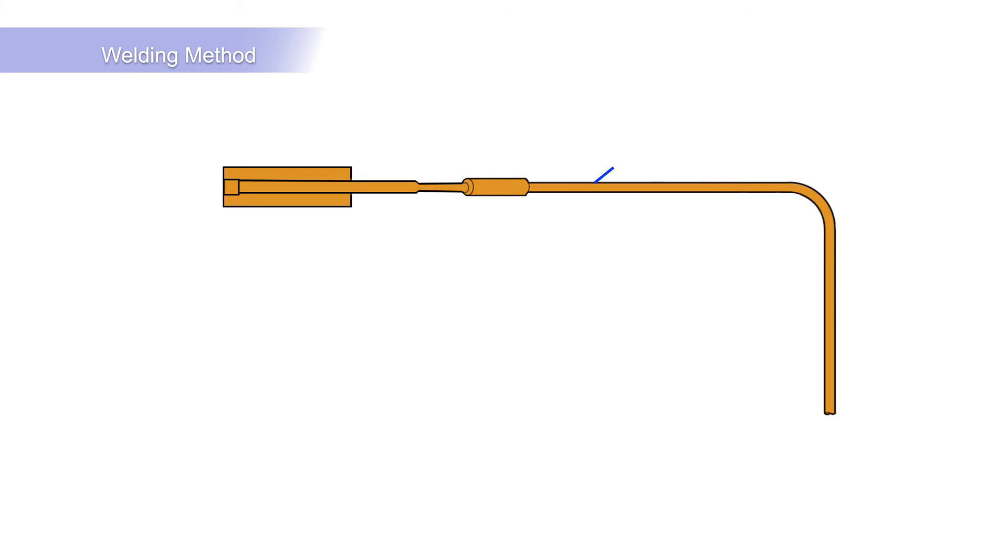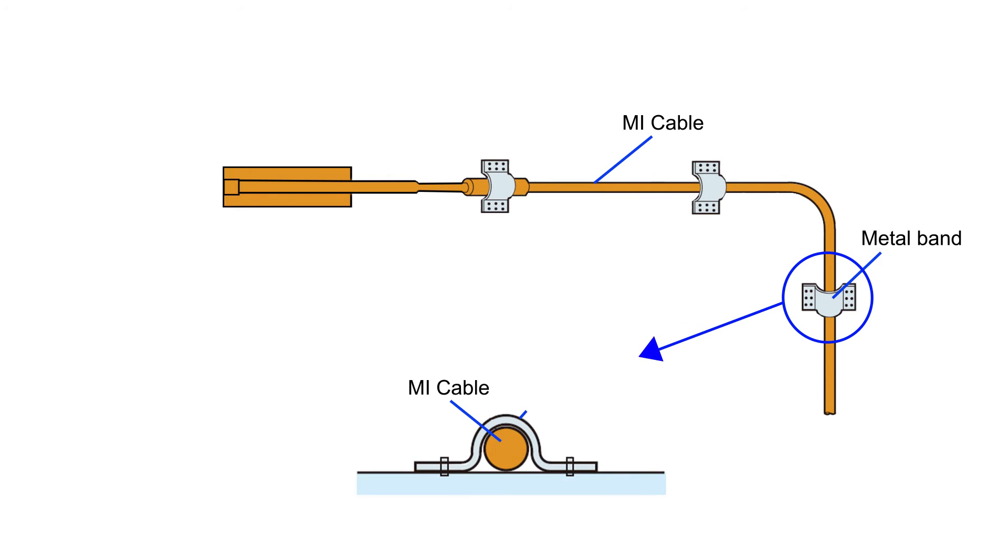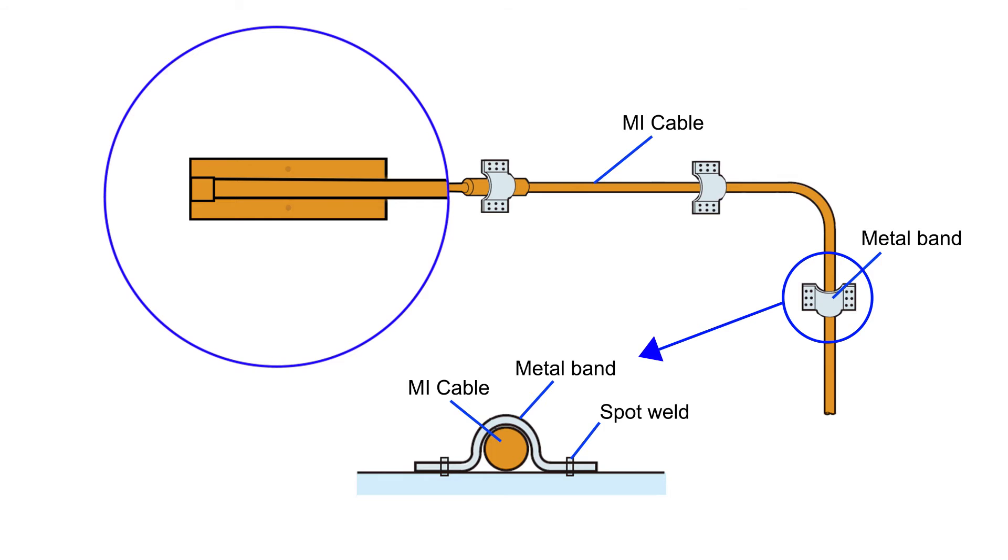The gauge and MI cable are mounted using a spot welding technique. Initially, the MI cable is secured with spot welding metal bands to stop the measurement point being affected by tension or twisting. The gauge is mounted with the welding done in a certain order to avoid issues and instability. Start at the center and work toward the cable, then finish with the outer end.